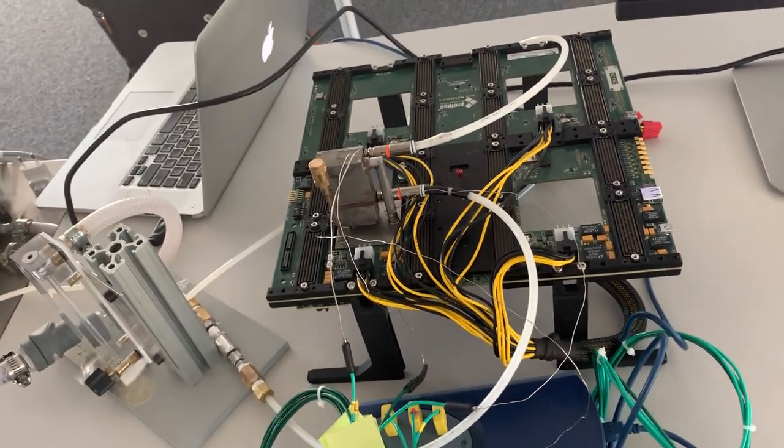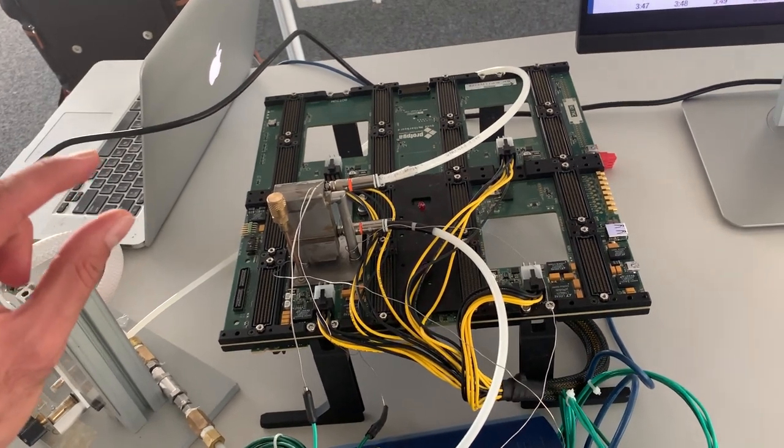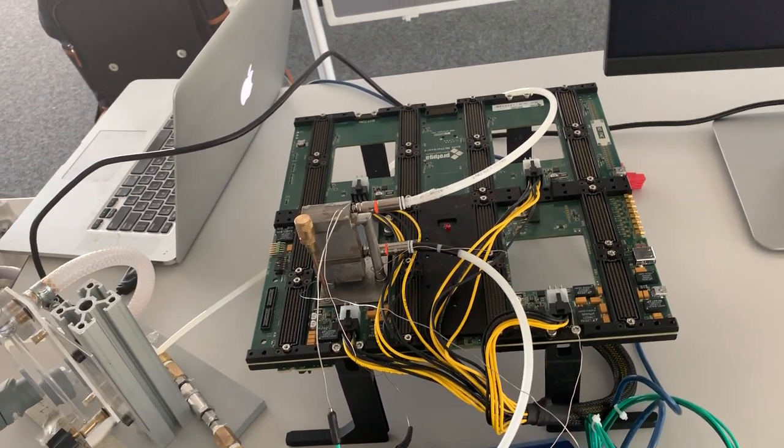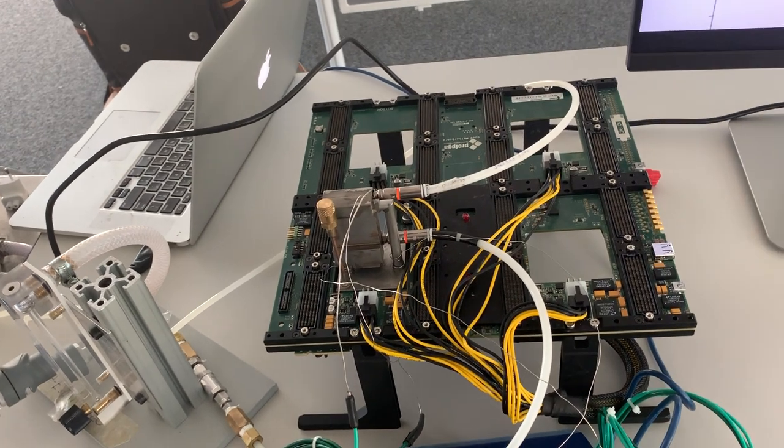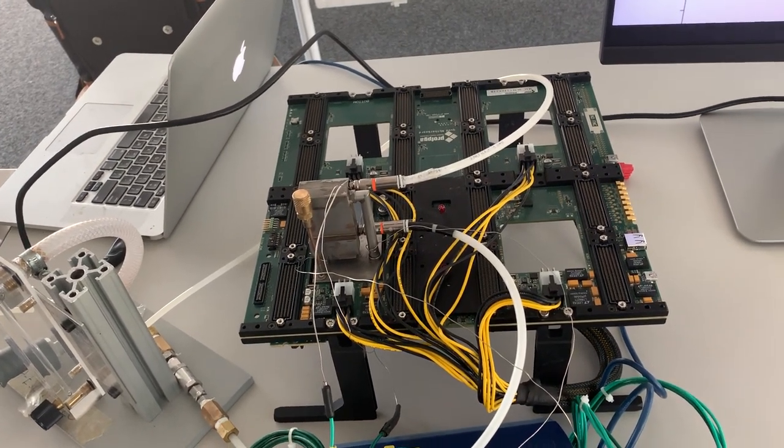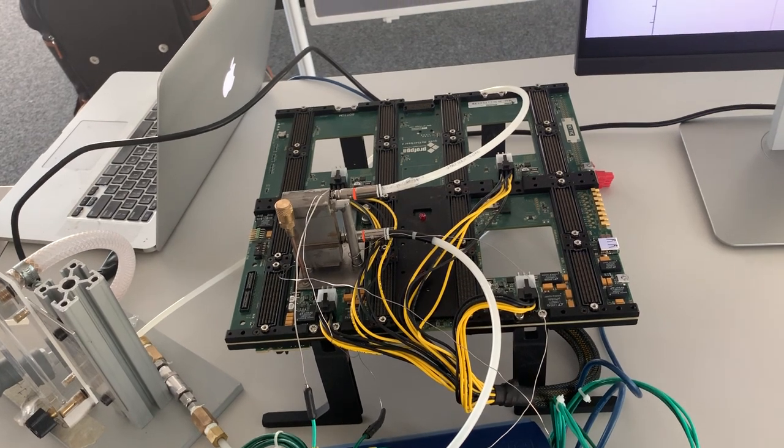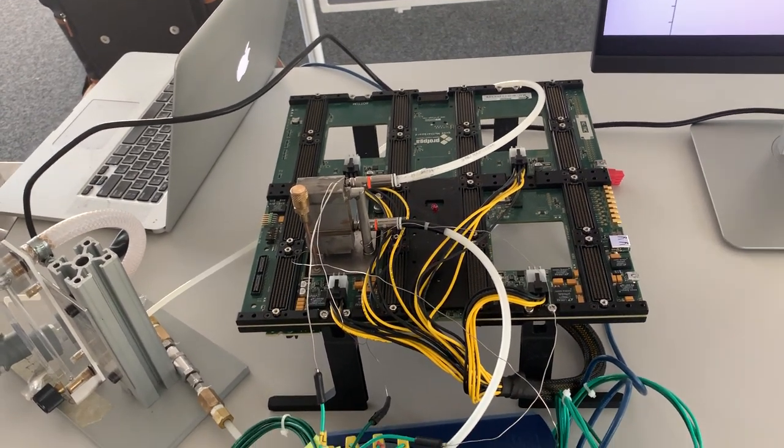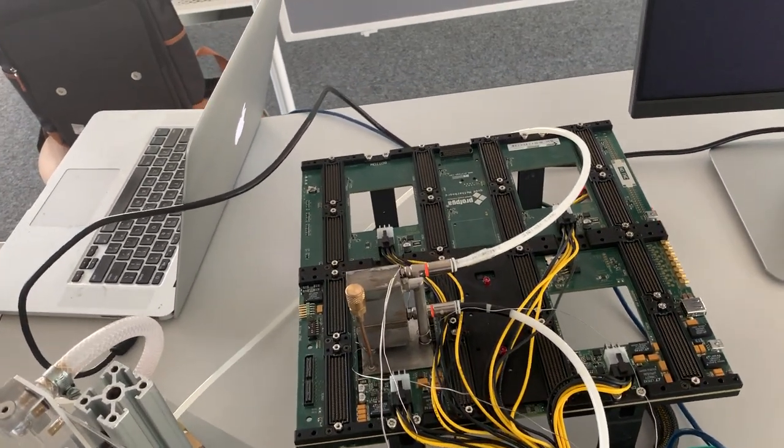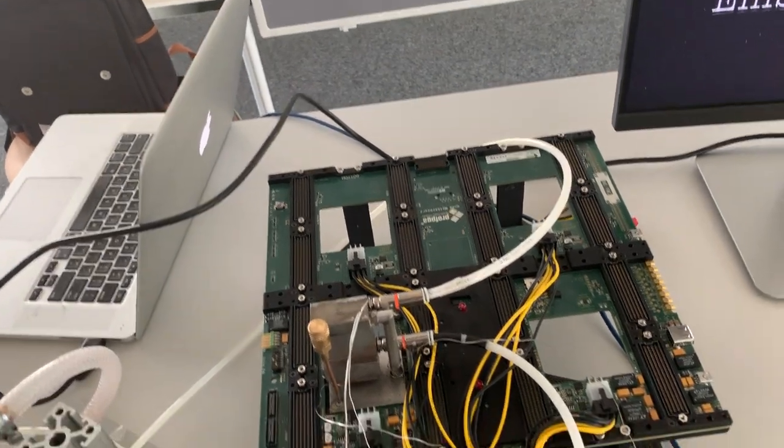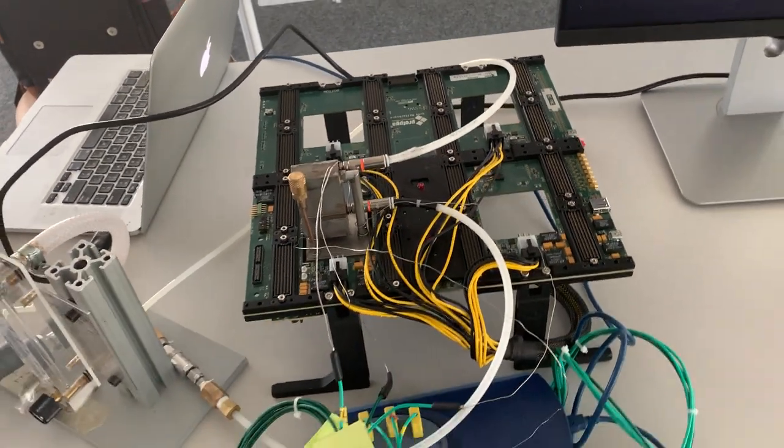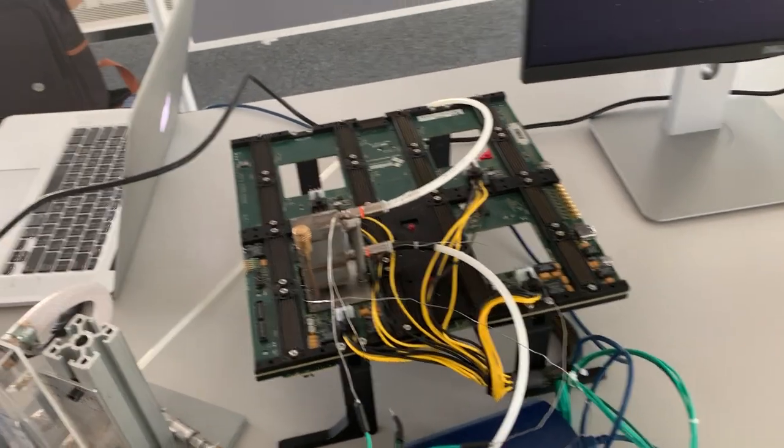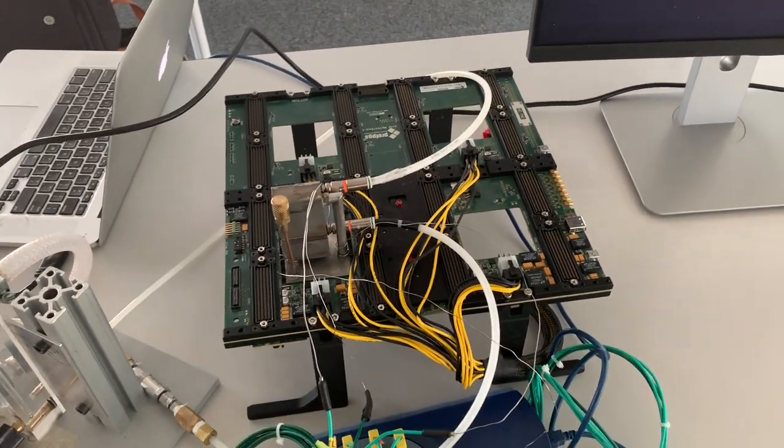And to cool down this amount of power, we need to consume very little amount of power. And then it means that the power usage effectiveness of our work is close to the optimal one. For the current prototype, we reach power usage effectiveness of 1.03. So I think I'm really happy.